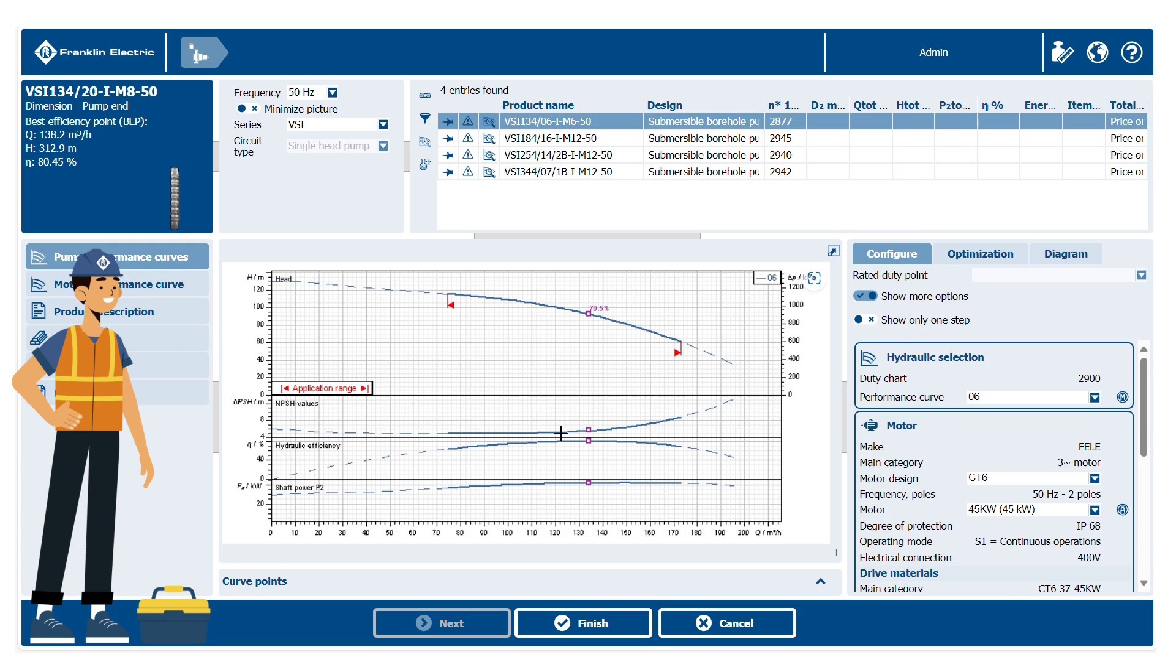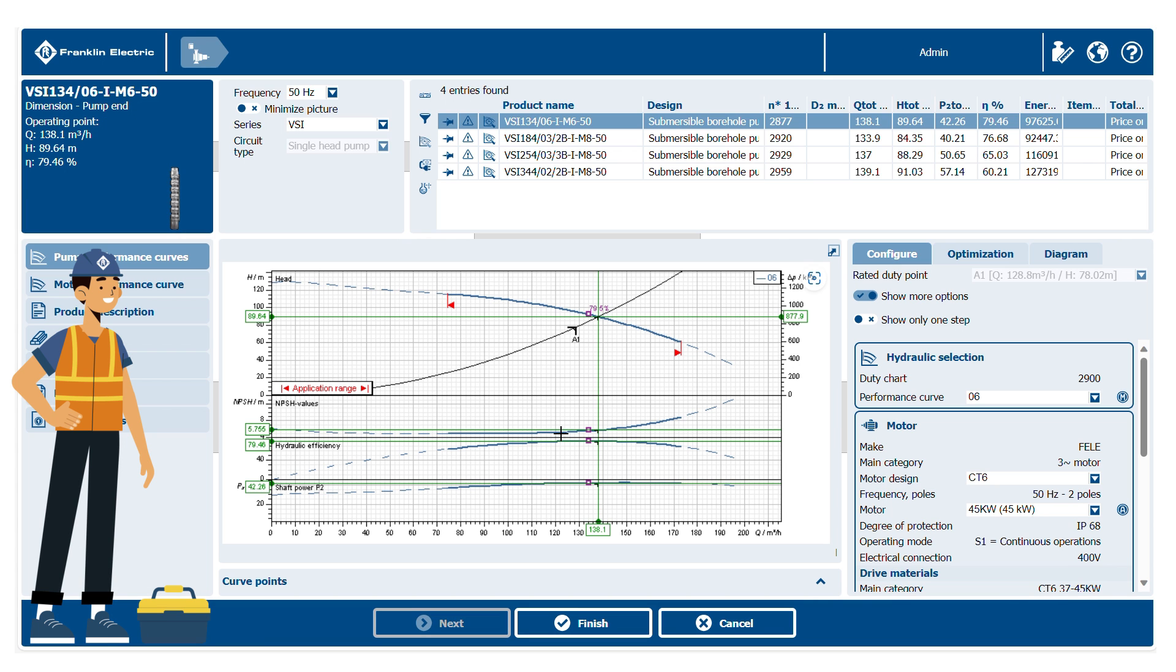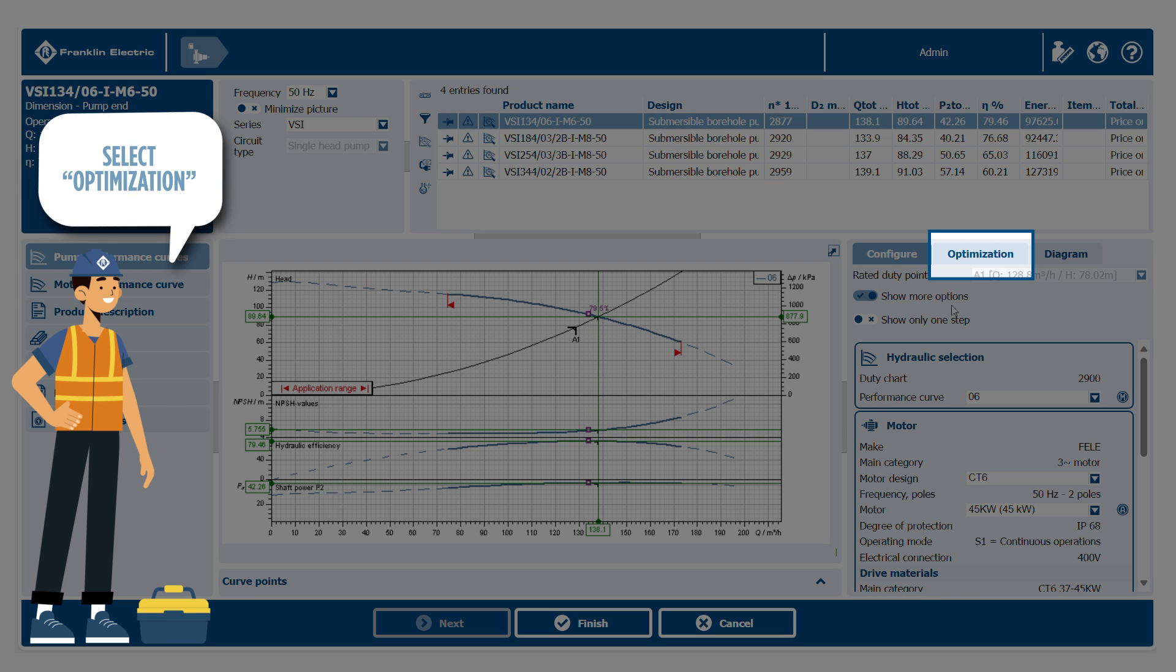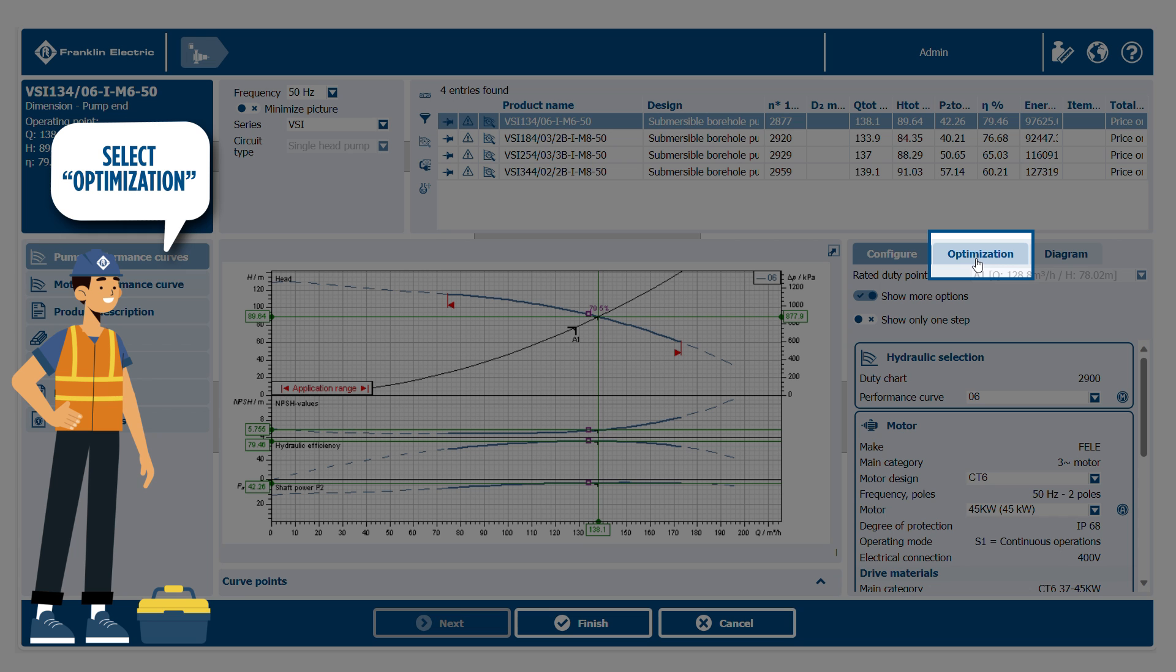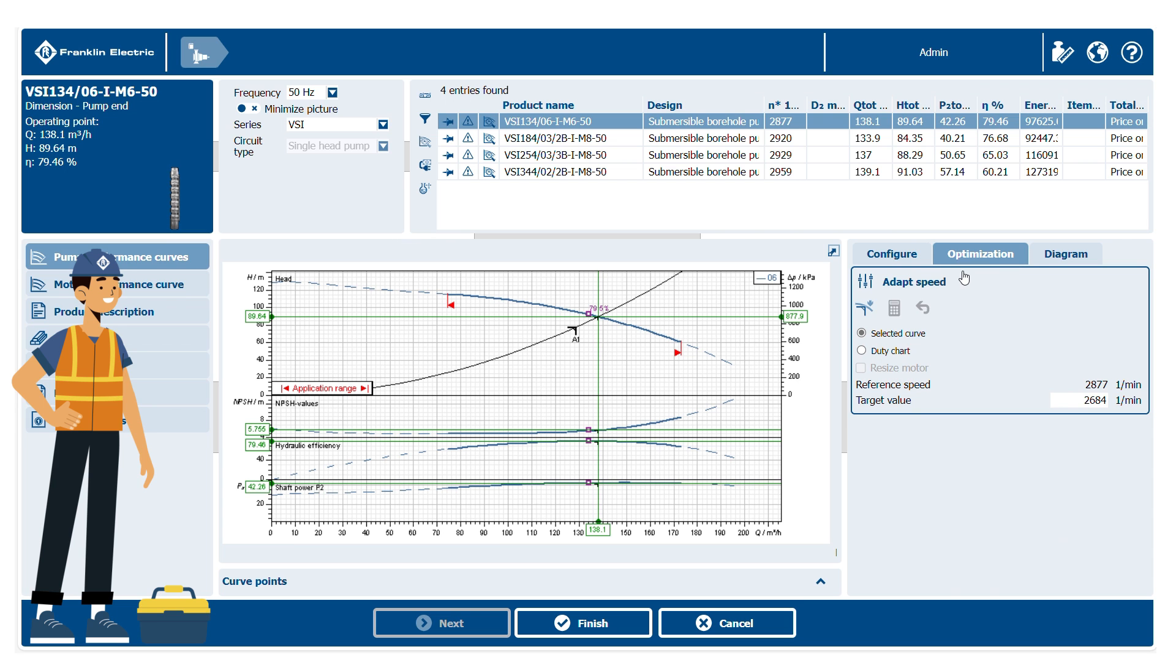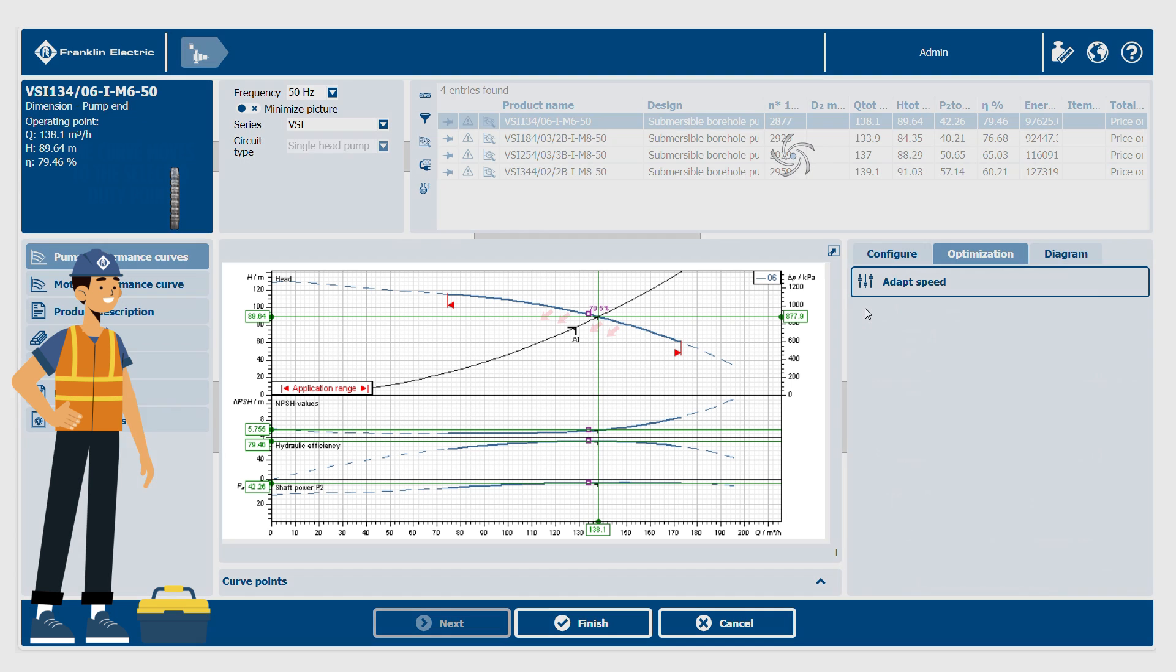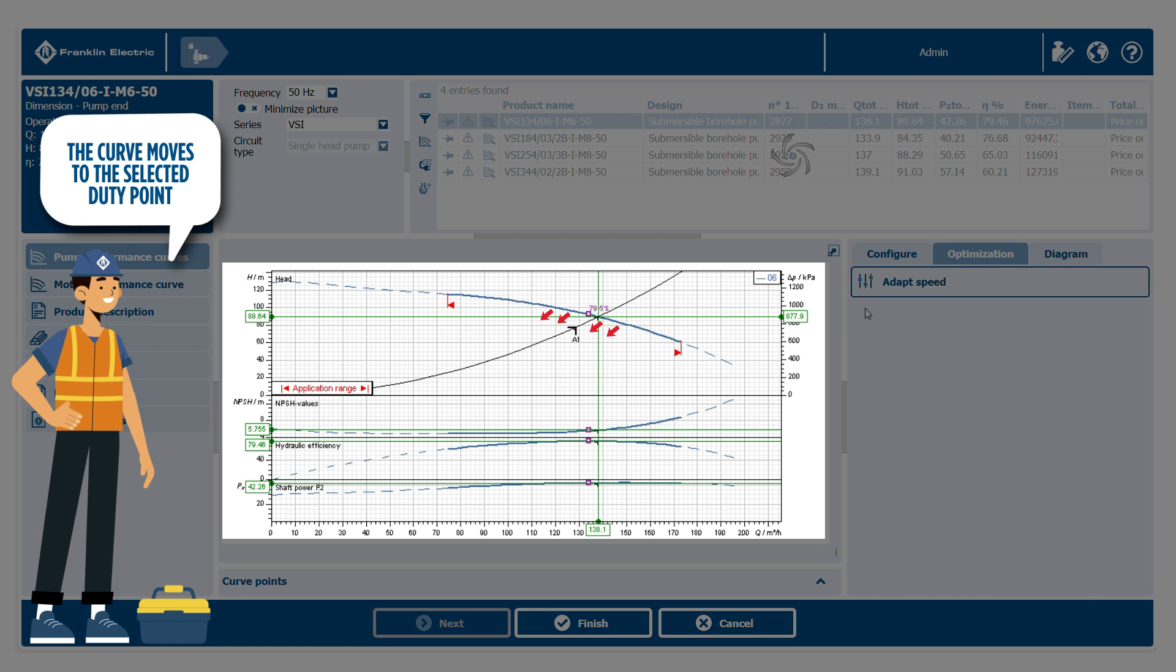Then the operating point will be displayed in the graphic and used for the calculation. The optimization function allows the pump performance to be recalculated in various ways. In this case, the pump speed is adapted. After selecting the icon, the curve is moved to the previously selected duty point. You can also notice that the reference speed data has changed and that the power and efficiency curves have been updated.